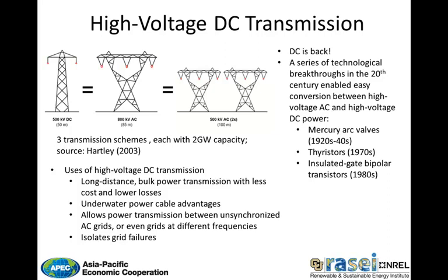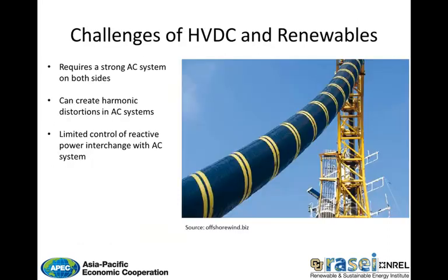DC interlinkages can also provide benefits to the existing AC power system. They allow power transmission between unsynchronized AC grids or even between AC grids running at different frequencies, which can increase system operator access to additional resources in an emergency. And in the event of a catastrophic failure on one AC grid, the DC line isolates the problem and does not allow interference with the other system.